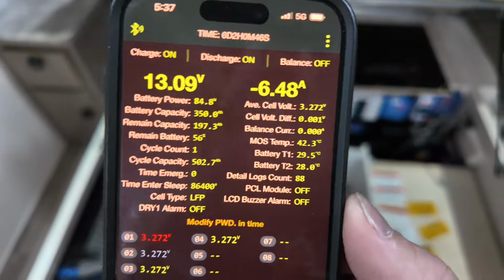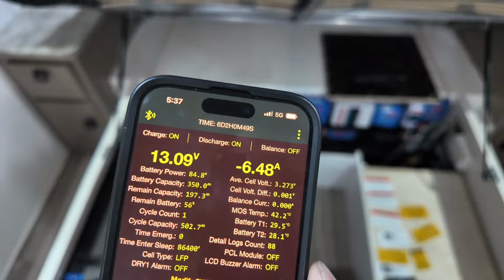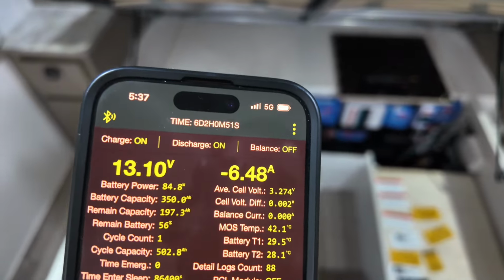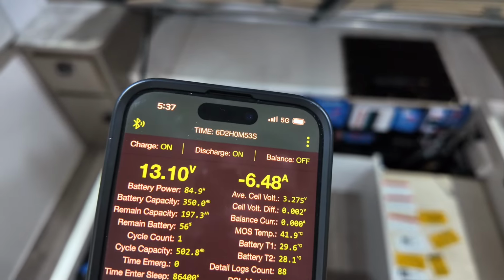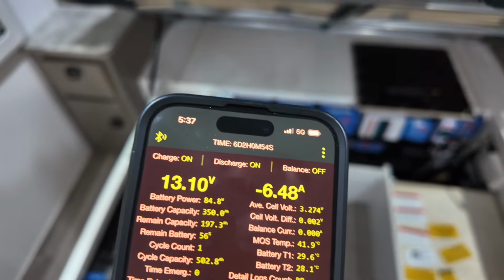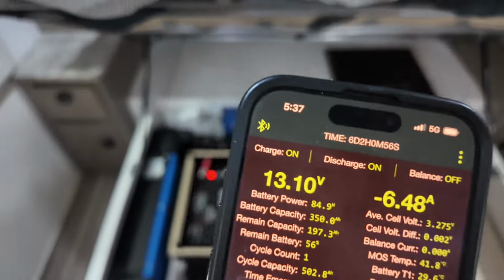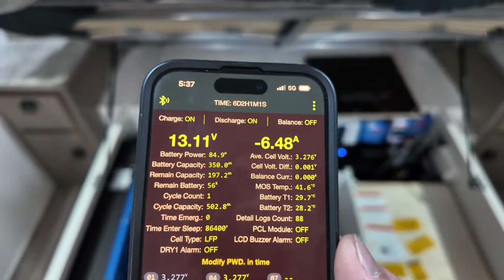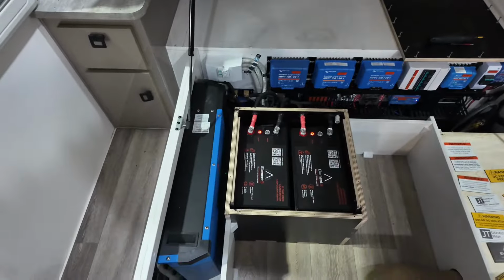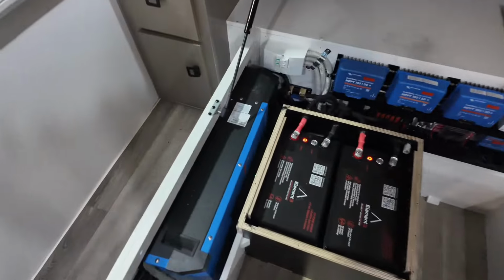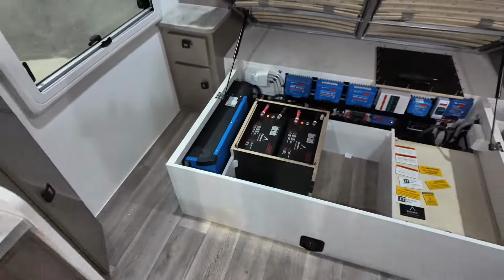On our batteries, we've got our MOSFET temperature at 42 degrees, which will turn off at 80, and then our battery temp 1, 2 - so you've got two cell temperature sensors as well. They're at 29 and 28, which is roughly what we're getting off the active terminal. And then down at the circuit breaker for the inverter, we're getting 30 degrees.